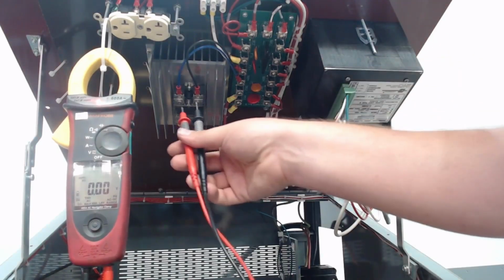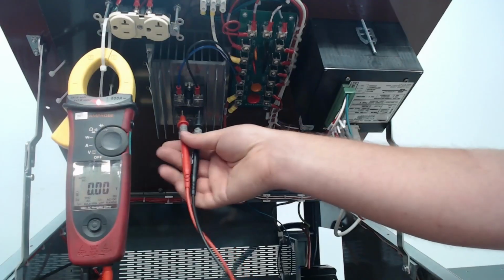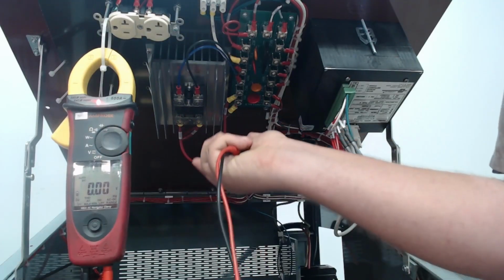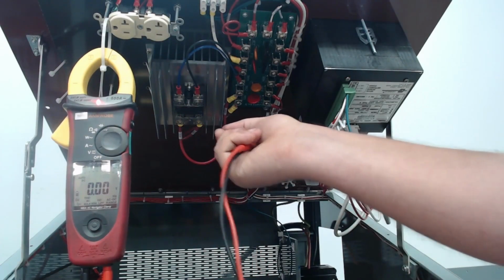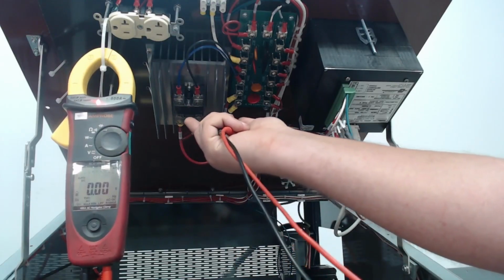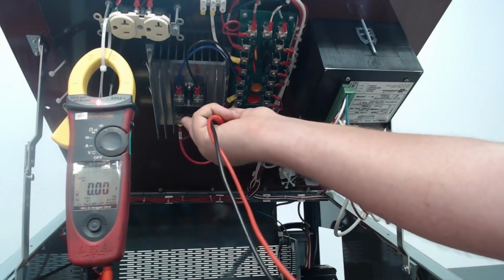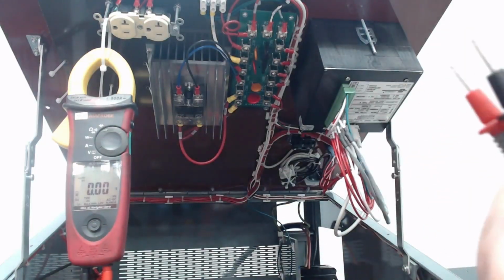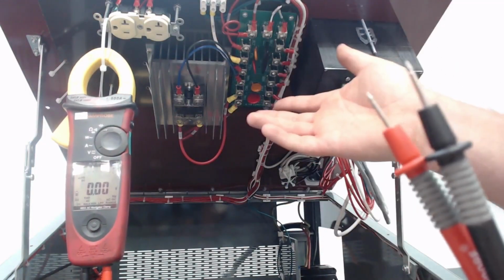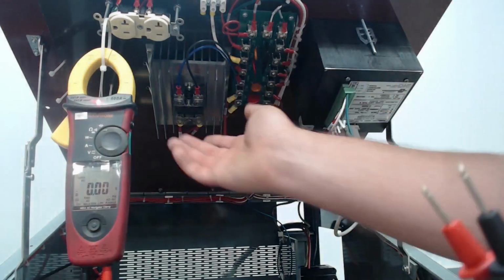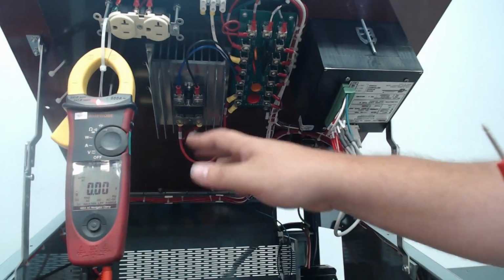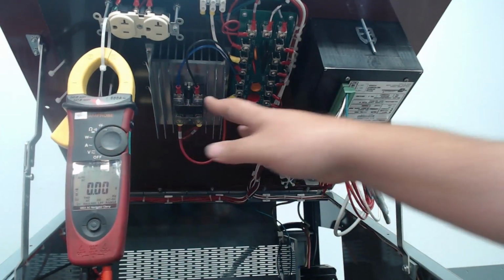Now, you can also check here on the SSR. You can look on the reading, take a picture, use your phone, zoom in. There is a positive on the part that needs to be positive, so you can check your polarity there. If your unit's been working in the past, then you don't have a polarity issue or it wouldn't have worked, but you can watch out for that.